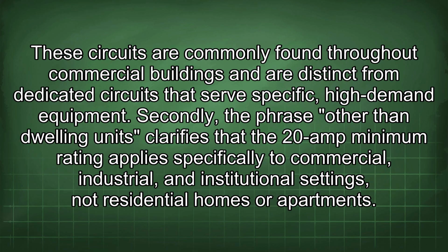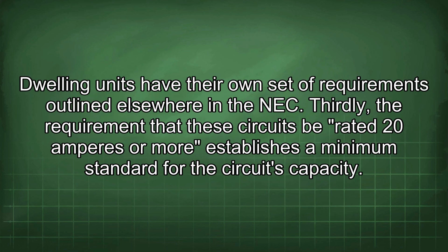Secondly, the phrase other than dwelling units clarifies that the 20 amp minimum rating applies specifically to commercial, industrial, and institutional settings, not residential homes or apartments. Dwelling units have their own set of requirements outlined elsewhere in the NEC.